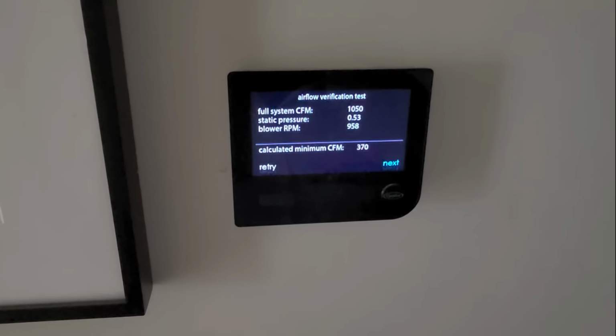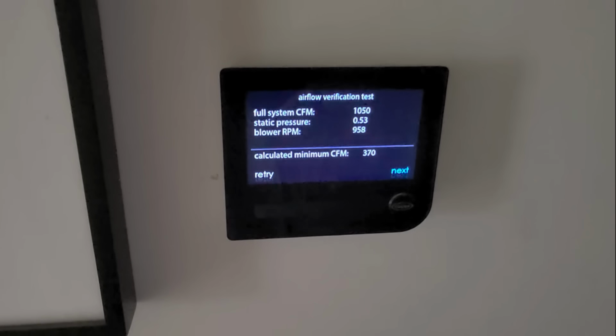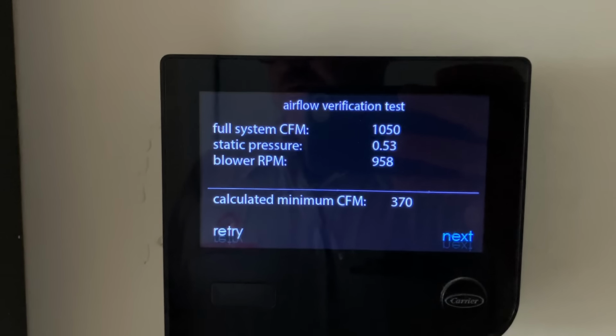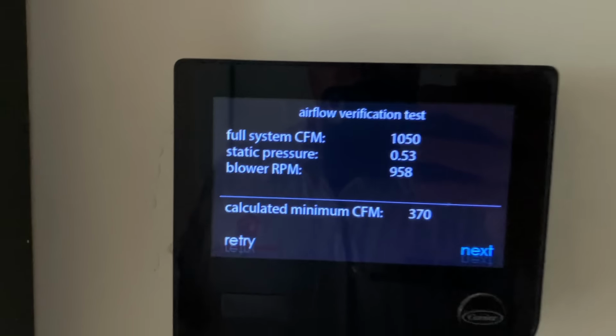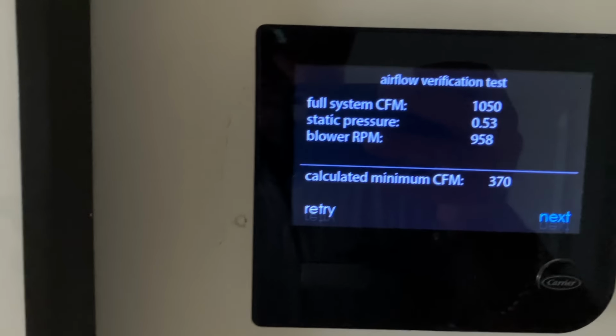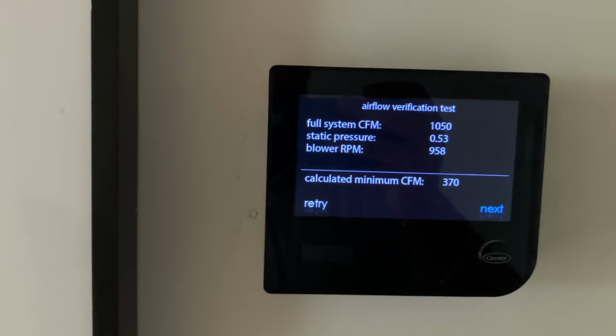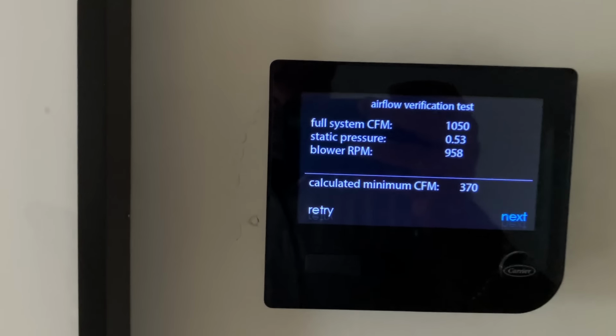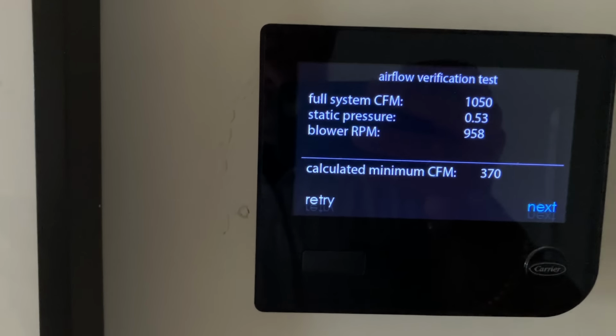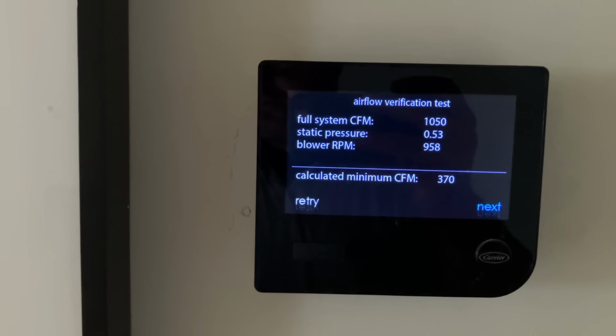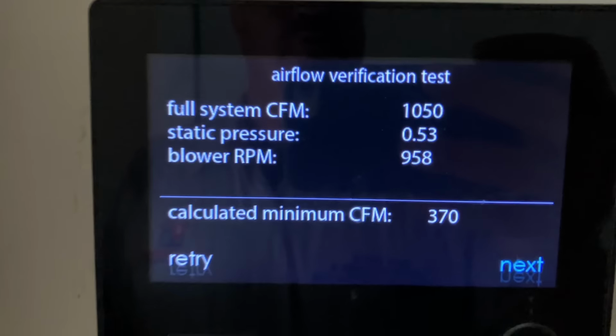Airflow verification. Yes. Let's check static pressure. Alright, filter's clean. Take a look at this. We just ran Carrier's airflow verification test on this 3-ton Infinity system, and we're moving 1,050 CFM. It's about 350 CFM per ton, and static pressure is 0.53. And the blower is running at 958 RPM to maintain that airflow.